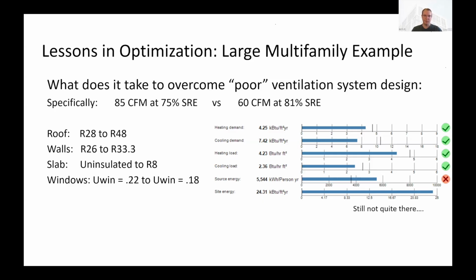We're still not down to the 4.1 kBTUs on the heating demand that we were just by switching out that ventilation flow rate. So hopefully you can see how important it is to have a very accurately dialed in ventilation rate and then properly choose the ERV that's going to be able to provide that at a pretty high efficiency, low fan power sort of situation. Because in this case, swapping that out, which includes changing nothing, just lowering the flow rate or dial on these ERVs, is the same as adding R20 to the roof and 2 inches of insulation around all the walls and the slab and a window upgrade, which is definitely not going to be cheap in this project with all the other requirements.